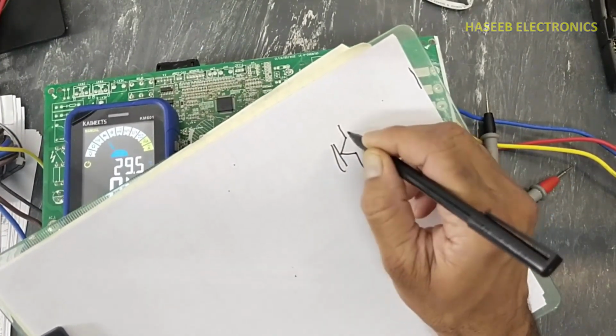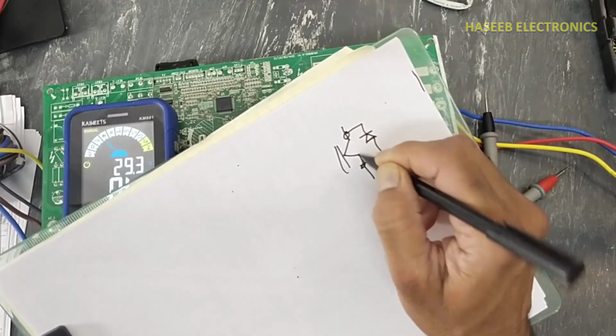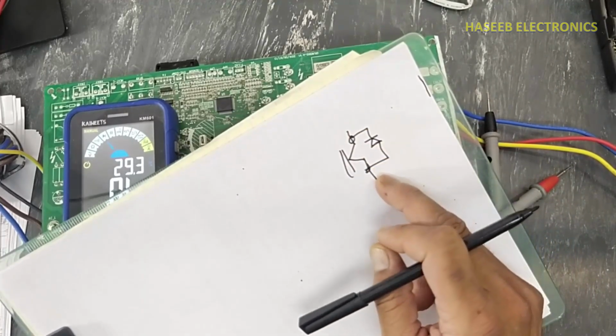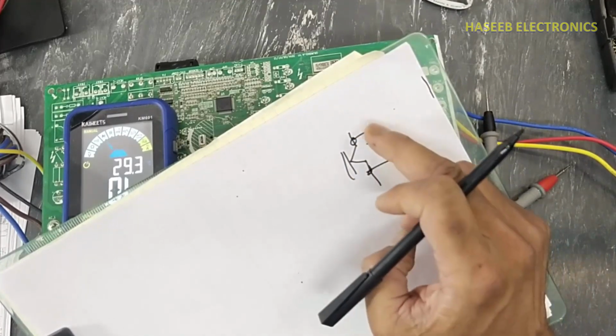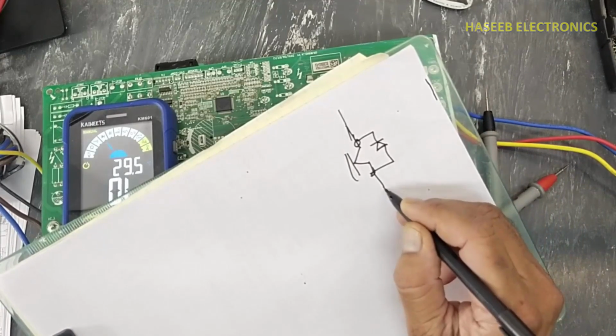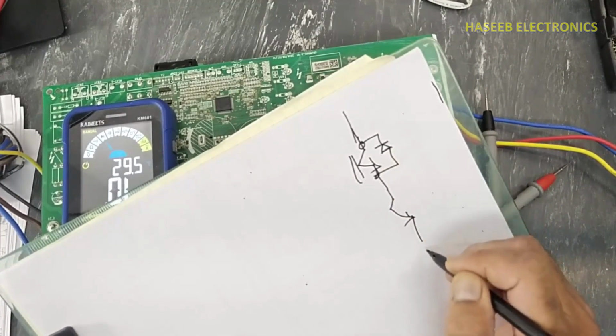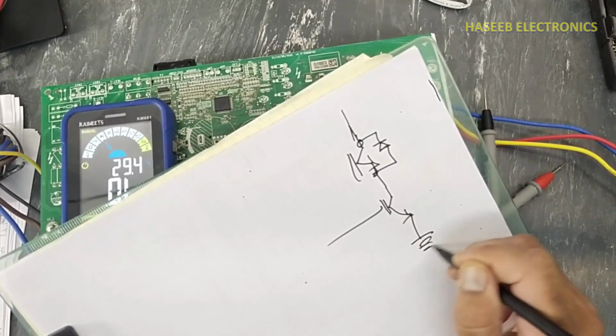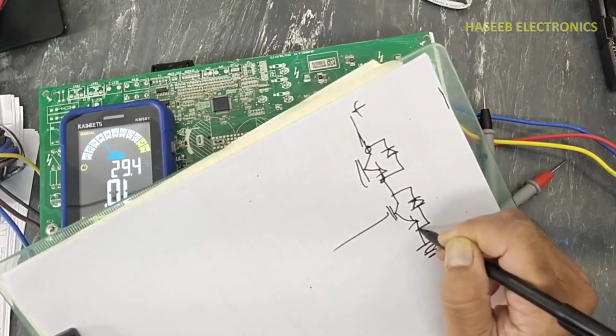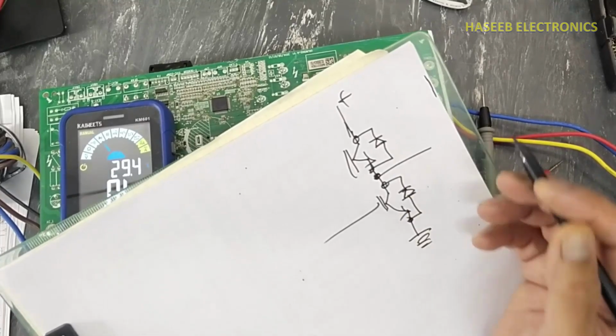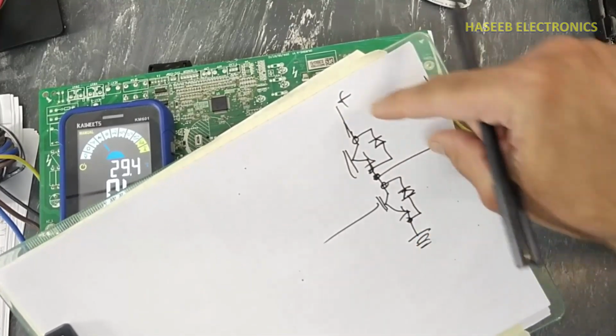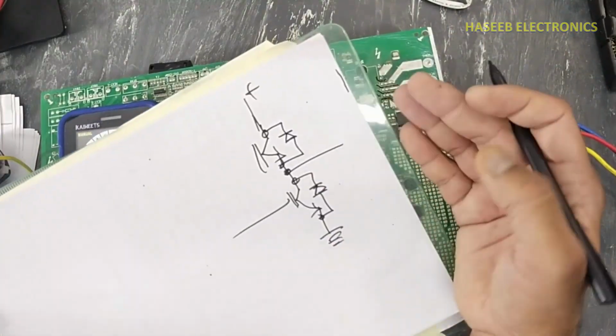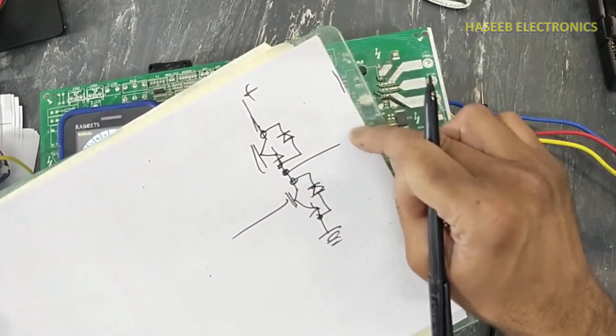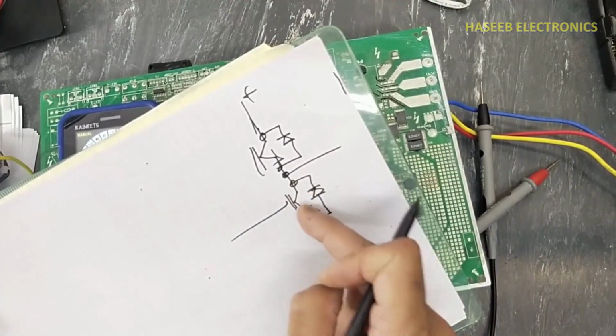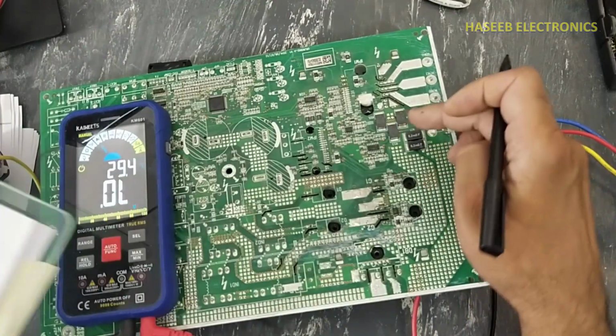Remember that we tested just only the IGBT, this rectifier, and we also verified the channel. If the IGBT is short circuited, it will give continuity. If this diode is short circuit, it will give continuity, because in each phase we have two IGBTs, negative, positive. And this is the output terminal, positive, negative. We tested these diodes. We have three sets in one IPM. As we tested, if it is giving continuity in this way, that we are finding diode drop voltage, that means this channel is silent because its gate is controlled by the internal IC.